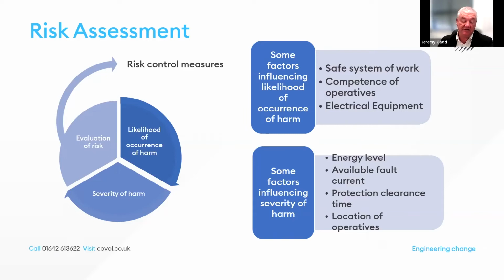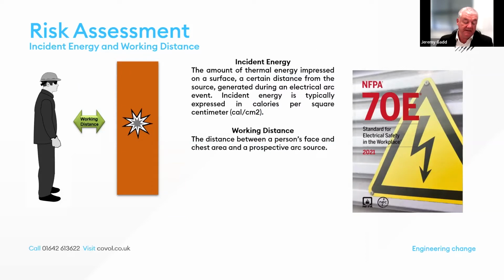We've previously discussed the factors influencing likelihood, such as their systems of work, competency, and the equipment itself. And we'll now look at those that contribute to the severity. Incident energy is defined as the amount of thermal energy impressed on a surface at any given distance during an arc. The distance, here defined as the working distance, is that between a person's face and chest area and the source of the arc. Both of these terms are defined in the standard NFPA 70E. The units of incident energy are generally expressed as calories per square centimetre.